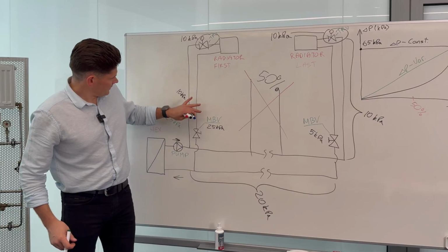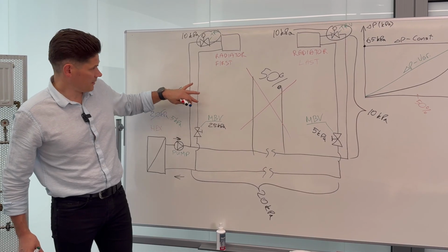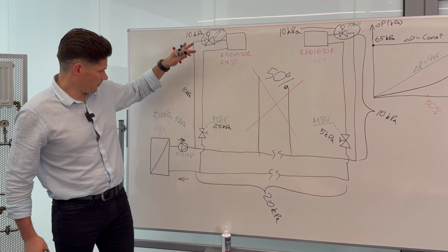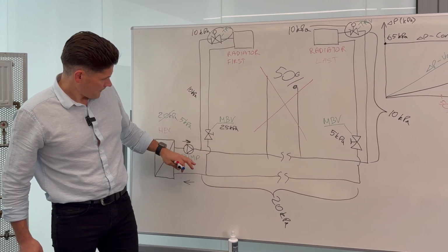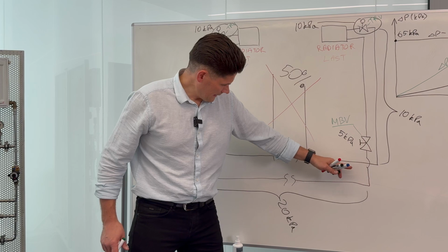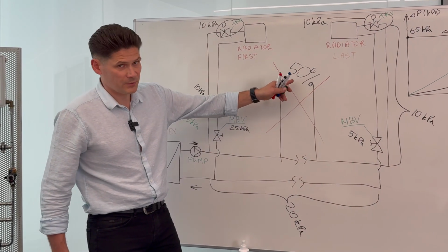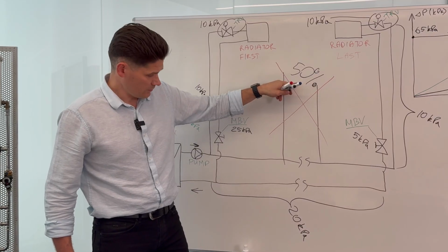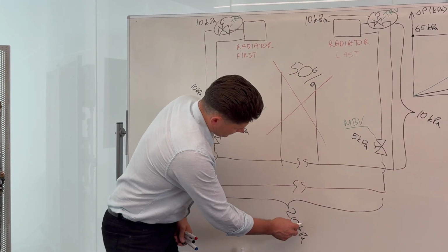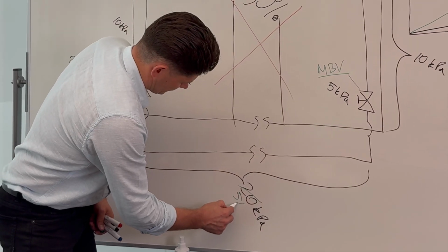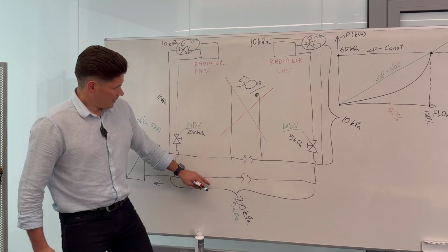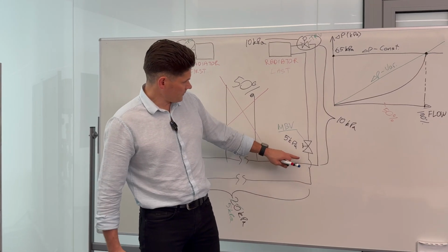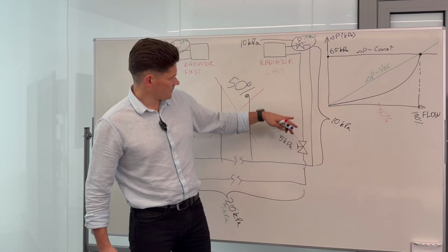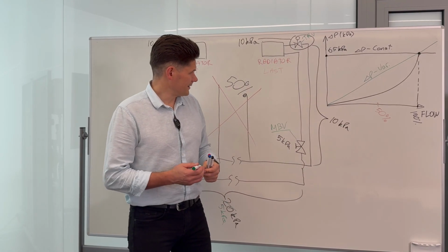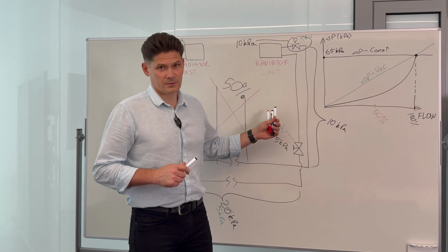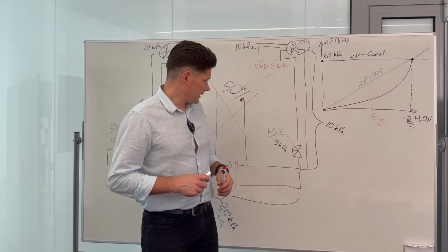Okay, let's say this riser is on the north side and it is working. It needs 100% capacity. It stays the same. I am passing on my supply line. So on the supply line, I'm missing 50% of the risers. 50% of risers are closed. So this means my 20 also becomes 5 kilopascals. Okay, and let's predict this riser is also working.